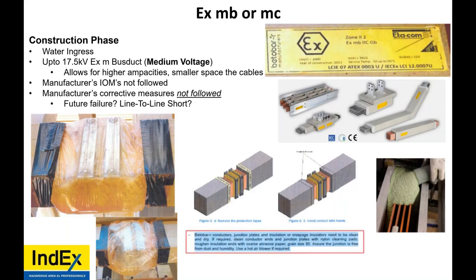So what are the chances of failure for this joint in the future? Well, the joints have a cement-type pouring done on each joint. Once it is done, it cannot be undone. So if you have a 1 kilometer run of this and you have a problem, you could be looking at millions and millions of dollars of ordering new equipment. You would have to take out this entire length of bus duct.